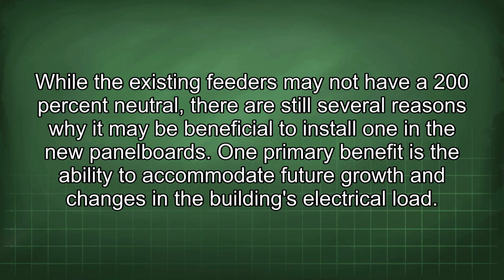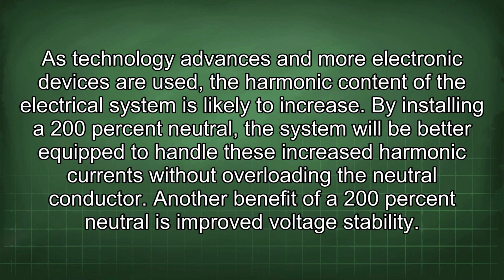One primary benefit is the ability to accommodate future growth and changes in the building's electrical load. As technology advances and more electronic devices are used, the harmonic content of the electrical system is likely to increase. By installing a 200% neutral, a system will be better equipped to handle these increased harmonic currents without overloading the neutral conductor. Another benefit of a 200% neutral is improved voltage stability.